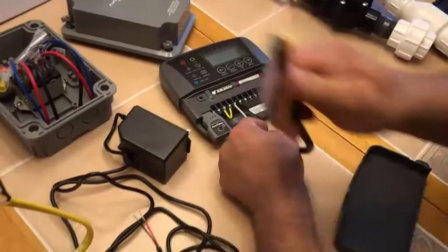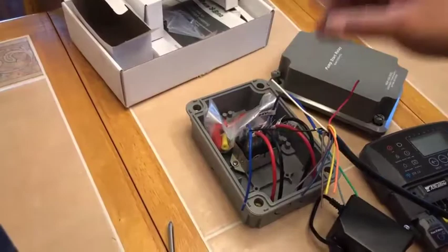As you can see, I have a white and a black here. When I wire this, I'll show it when I'm done—I'm going to have the white to the common and the black to the pump, because I'll have white and black over here connecting to here, and then another white and black that actually goes to the pump. So I'll have white and black going from here to wherever the black one is. I'll have the white and black connecting to these blue leads. Because this is low voltage, it doesn't matter which side the black connects to, as long as you're completing the circuit with the wires connected. I'll show that. The rest of the wires are intended for handling the zones.